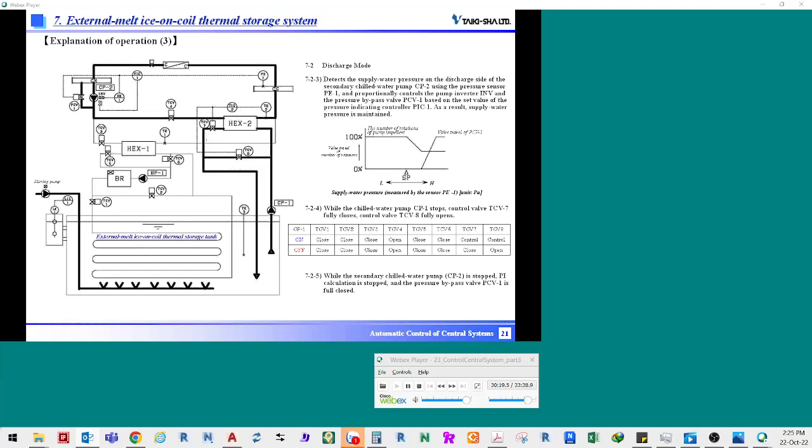The rated flow rate of the pressure control valve used under inverter control is often selected based on 30 to 40% of the rated capacity of the pump. If you select the rated flow rate of the pressure control valve based on the rated capacity of the pump, if the pressure is controlled by the pressure bypass valve, and if you cancel inverters, you may reduce the initial cost.